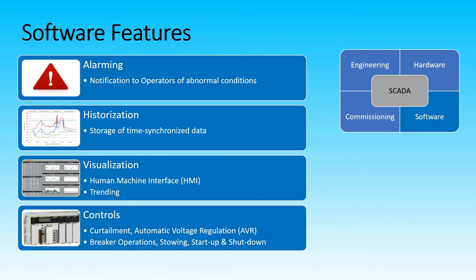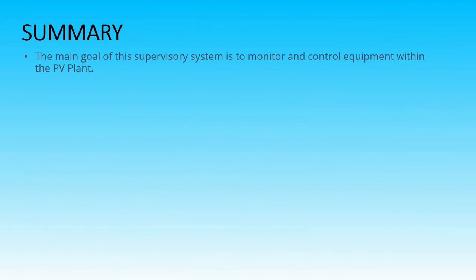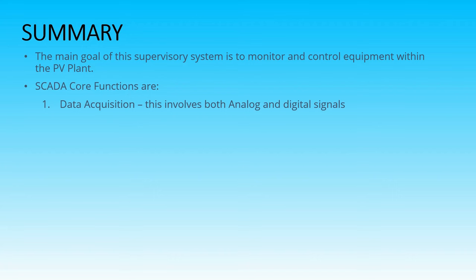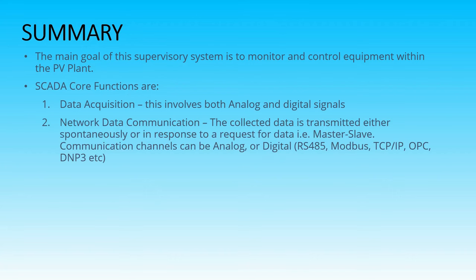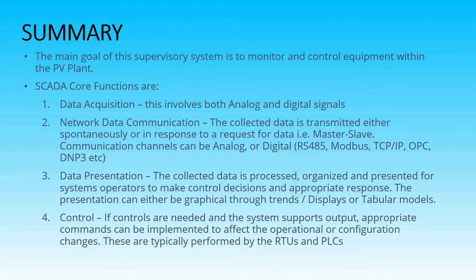For controls, ideally we would need a fast-acting and fault-tolerant grid control system. This should have features like closed-loop curtailment, power factor, reactive power, and ramp rate controls. As a summary, the main goal of this supervisory system is to monitor and control equipment within the PV plant, and its four core functions are data acquisition, network data communication, data presentation, and controls.